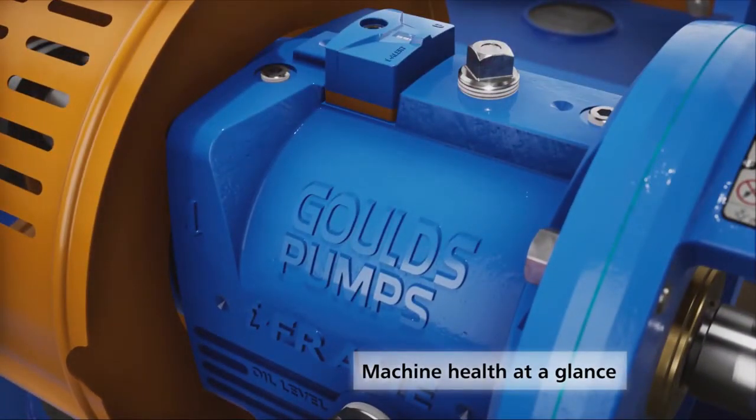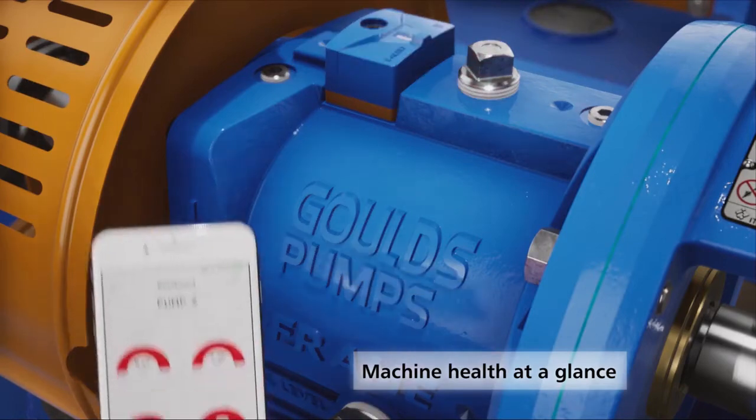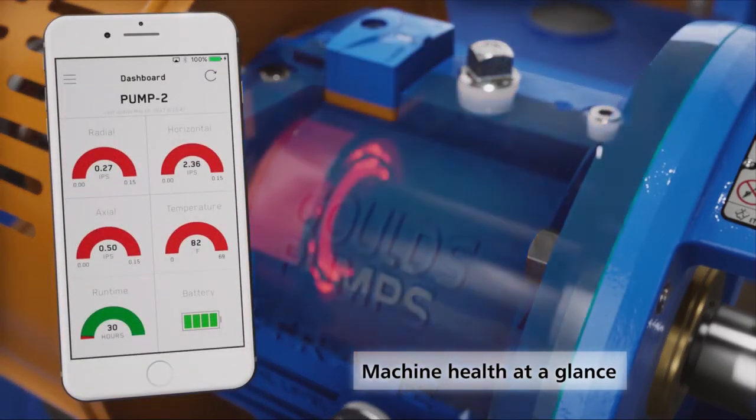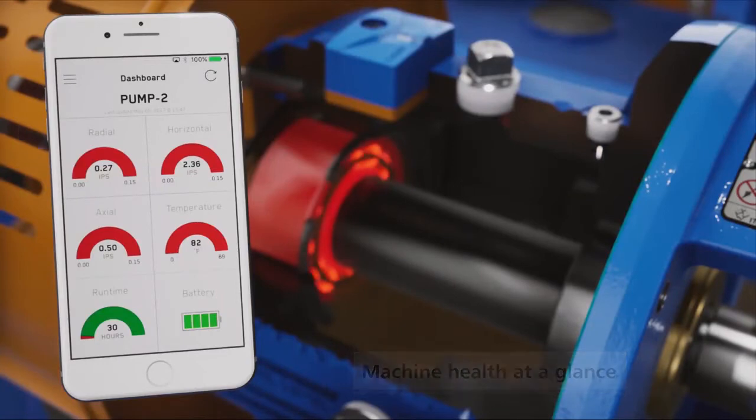If the vibration or temperature rises above the set limits for two consecutive readings, the iAlert 2 will begin to blink red and broadcast an alarm message. The broadcasted alarms can be picked up by Bluetooth-equipped phones or tablets in the area.